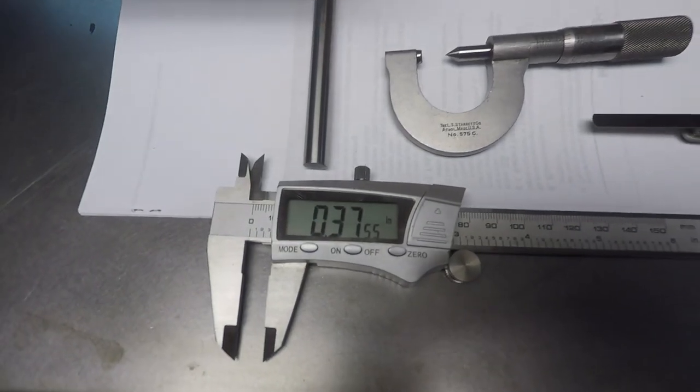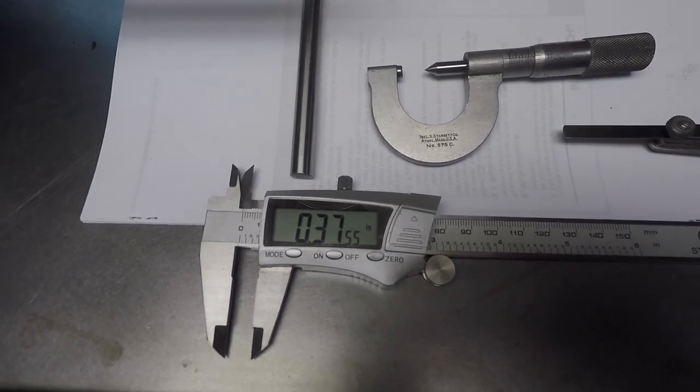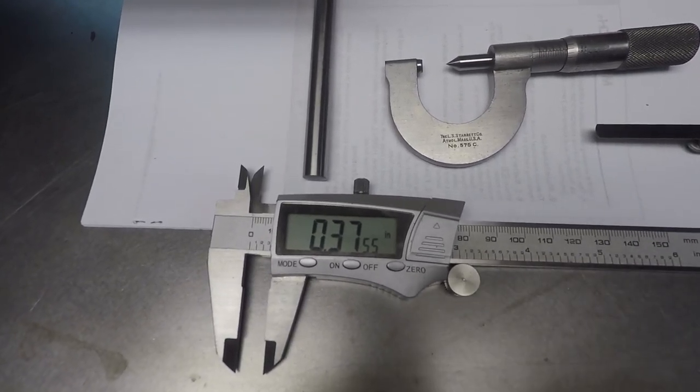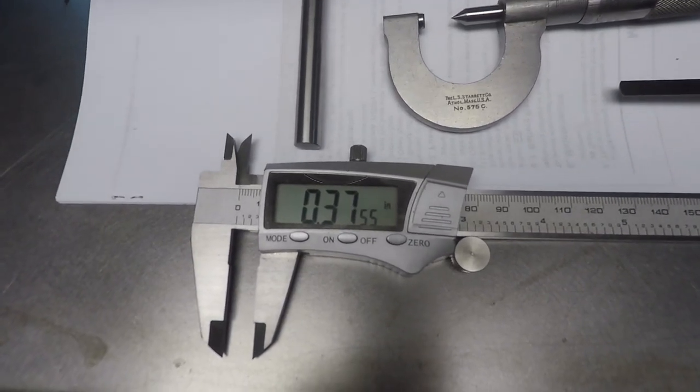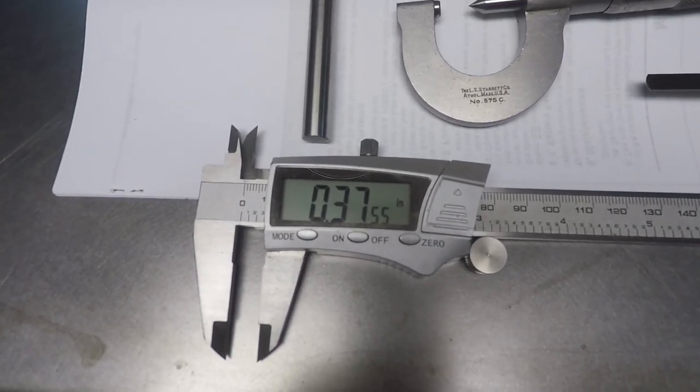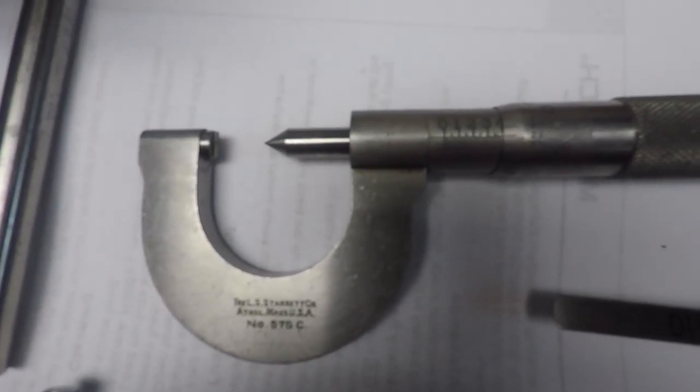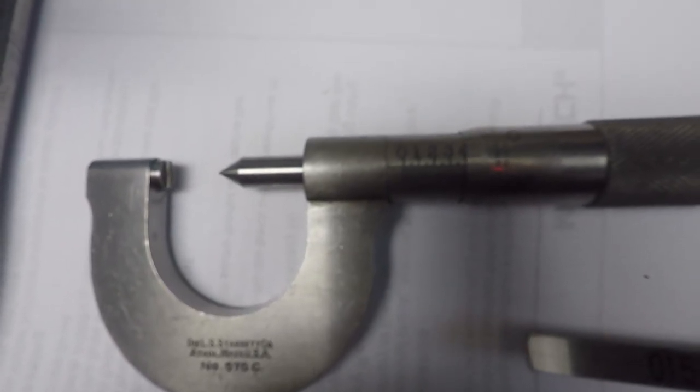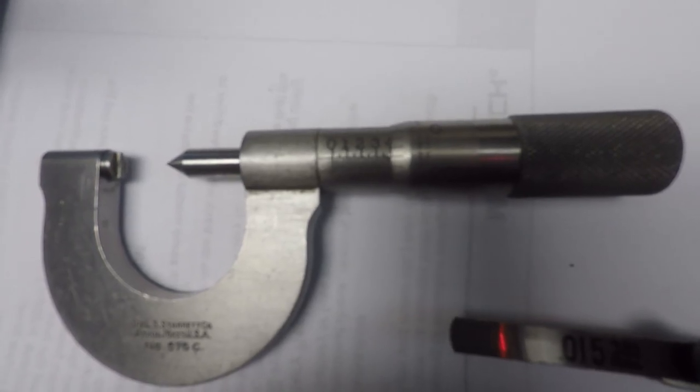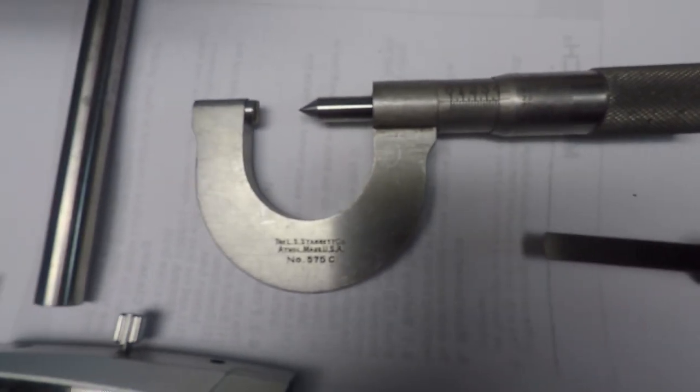Again, here for instance is the measurement of the three-eighths bar, which should be .3750. The digital is showing an extra five ten-thousandths, I'm not so worried about that, but the Starrett micrometer is reading twenty-one thousandths over the appropriate measurement. I don't know if you can see that, but we're...